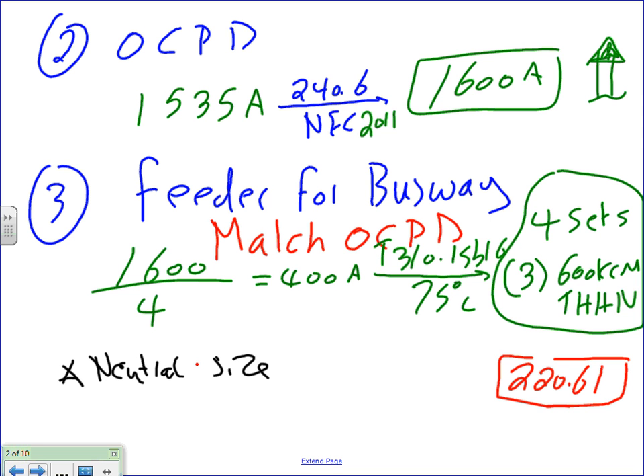Now neutral, I might not need a neutral at all. So the neutral could be zero here, no neutral for this. If all of them are three phase, no neutral. But I'm gonna size it, if I need a neutral, what should I do? Most of these guys don't have a neutral. All of them are 480, and you plug them in. If I need a neutral, here's where I go.